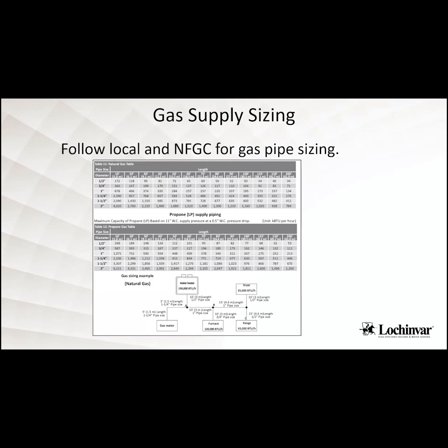So this is the National Fuel Gas Code gas pipe sizing. This is at a 1/2 inch drop. I know everybody's usually pretty good at sizing gas lines, but we just want to make sure that we do have enough gas. With 199,000 BTUs, we want 199,000 BTUs delivered to the bottom of the unit. These do have a negative pressure gas valve with an air gas mixing fan, so we are in that negative pressure, but we are not going to be able to pull 199,000 BTUs worth of gas through a 1/2 inch line that's 100 feet long.